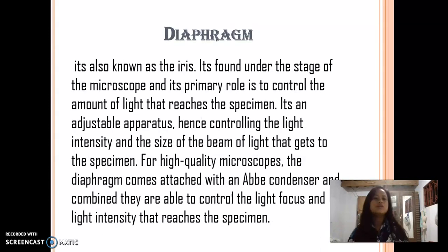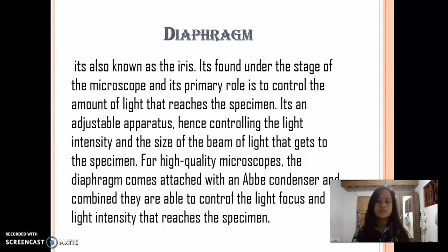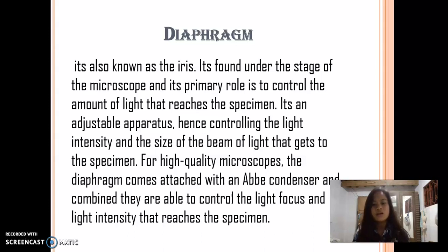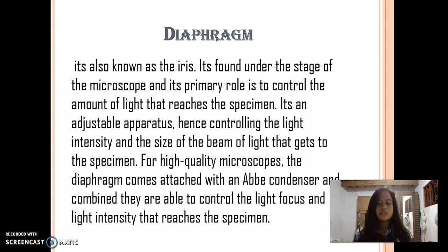Diaphragm, also known as the iris — it's found under the stage of the microscope. Its primary role is to control the amount of light that reaches the specimen. It's an adjustable apparatus, hence controlling the light intensity and the size of the beam of light that gets to the specimen. For high-quality microscopes, the diaphragm comes attached with the Abbe condenser, and combined they are able to control the light focus and light intensity that reaches the specimen.